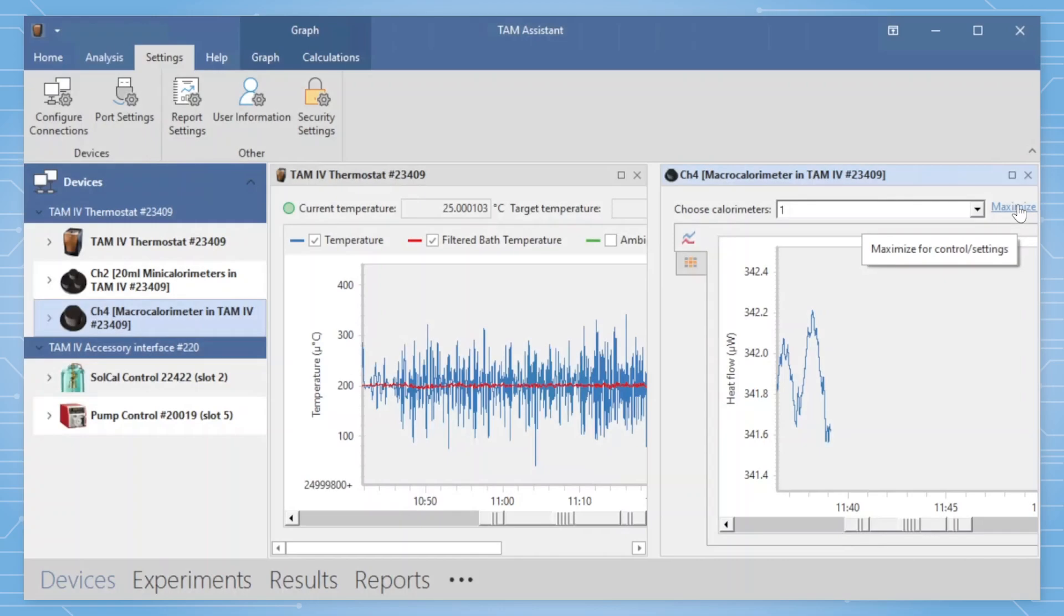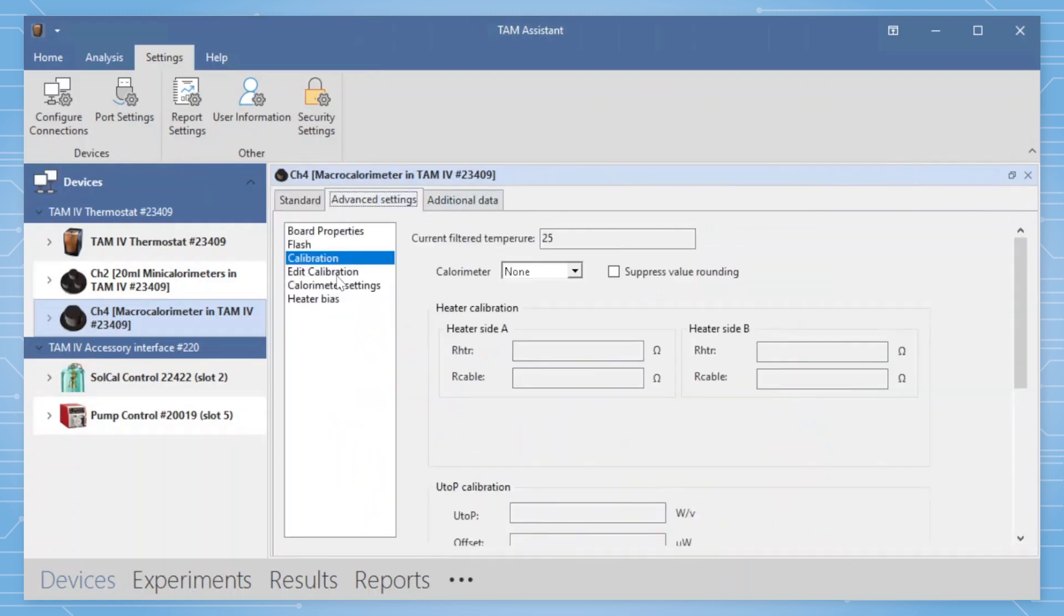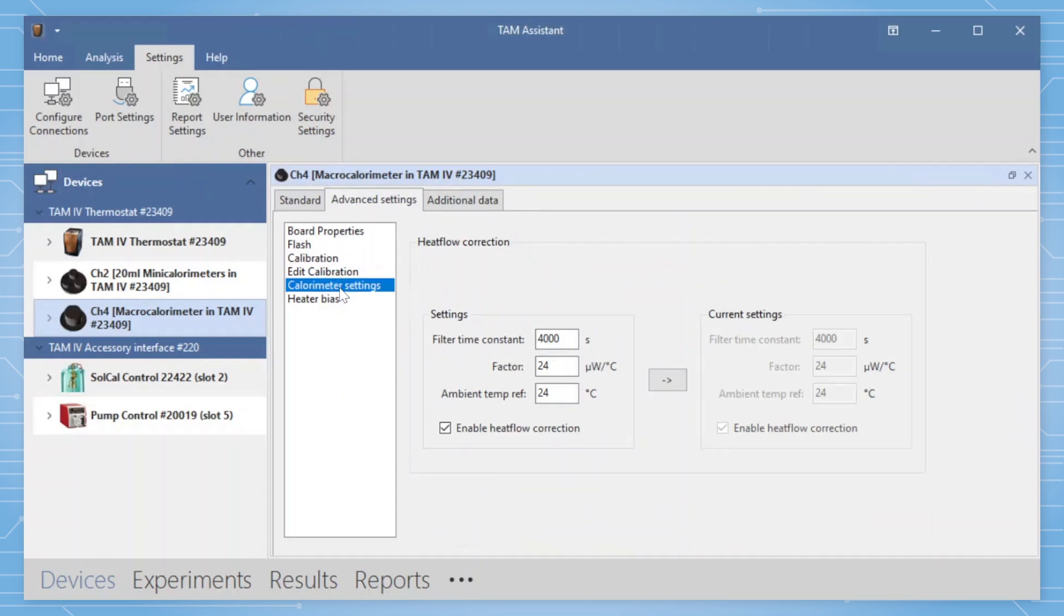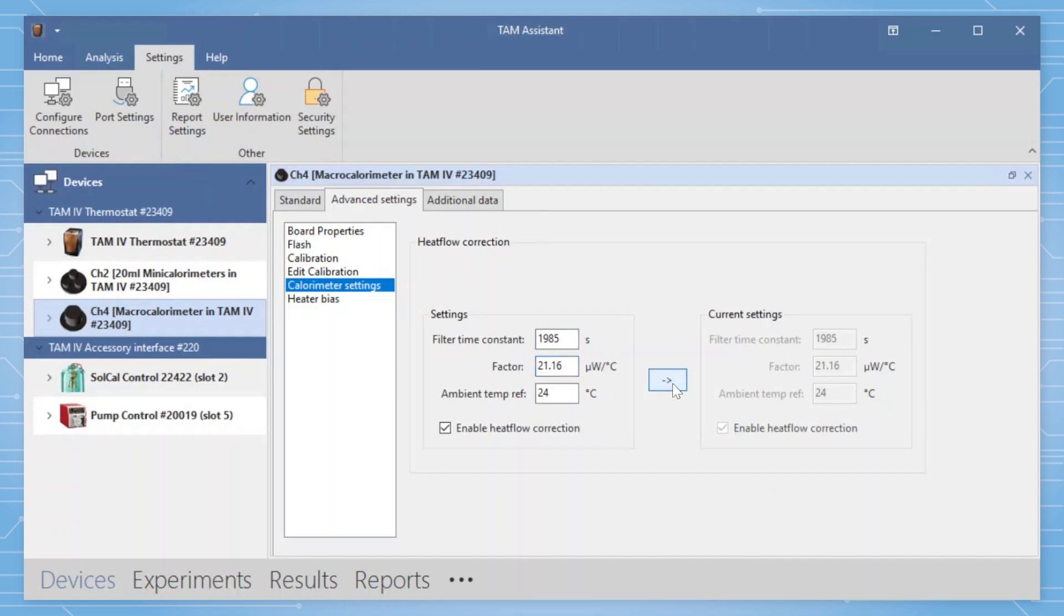Go back to the TAM Assistant that is controlling the calorimeter. In the advanced settings tab, select calorimeter settings in the left panel. The heat flow correction window will be displayed. Make sure enable heat flow correction is checked. Enter in the filter time constant and heat flow dependency factor that was calculated in Excel. To apply, click the arrow in the middle. The calorimeter signal will now be corrected based on the filter time constant and heat flow dependency values applied.